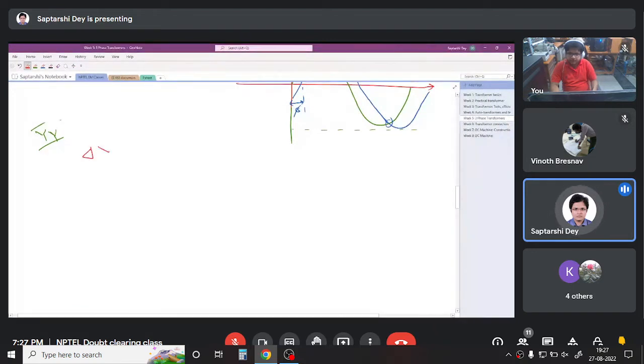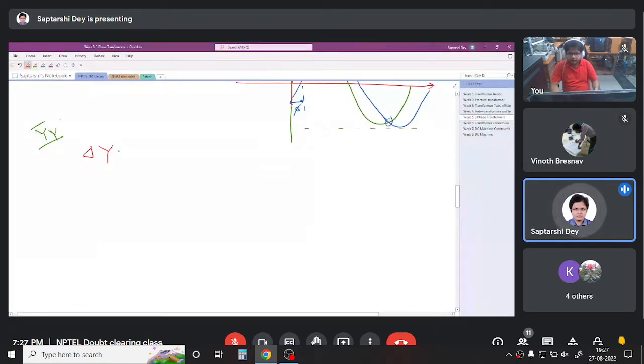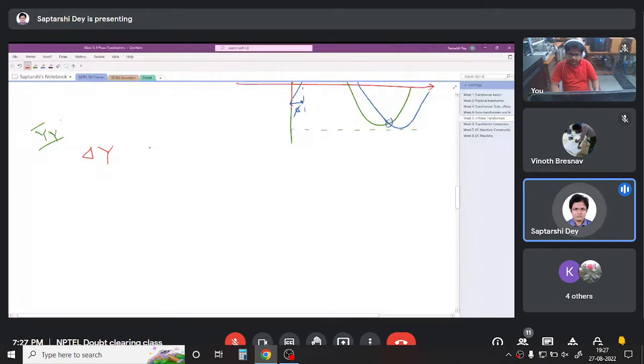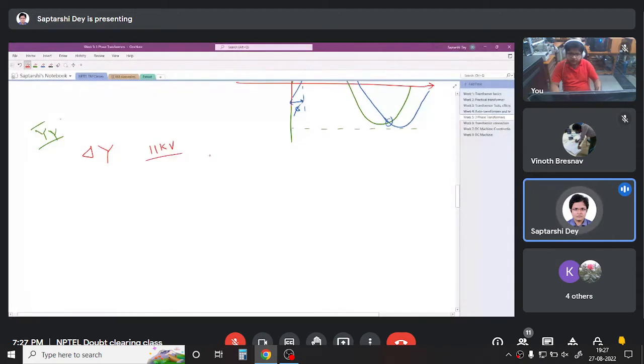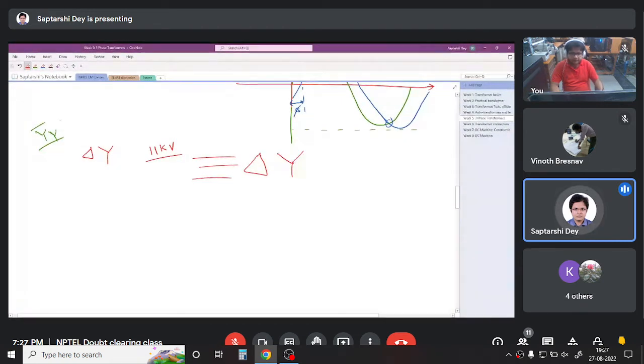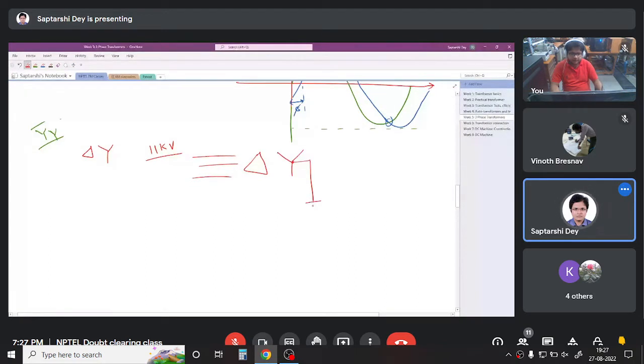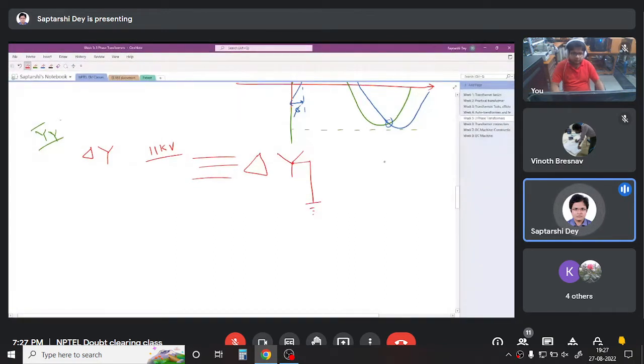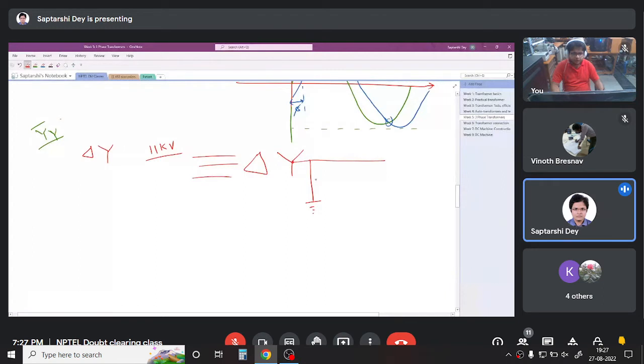The transformer that you see in your locality on the poles, all of them are delta star. The 11 kV line that comes to your locality goes to the delta primary of the transformer, and the secondary is star. So this neutral is grounded. This neutral is nothing but the neutral wire that comes to your house.